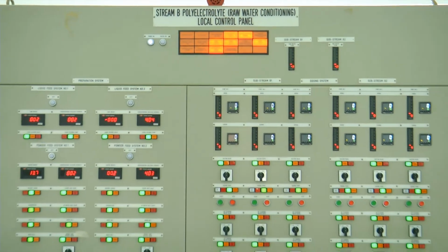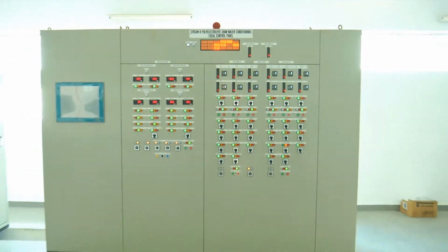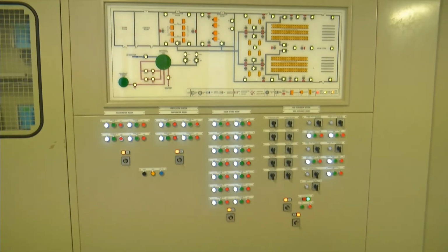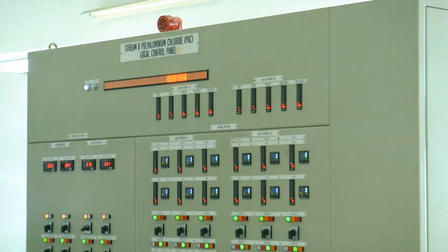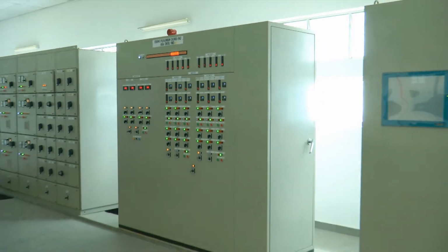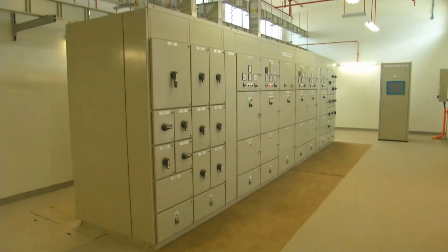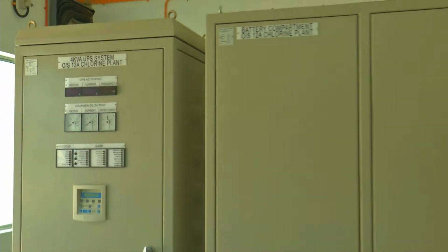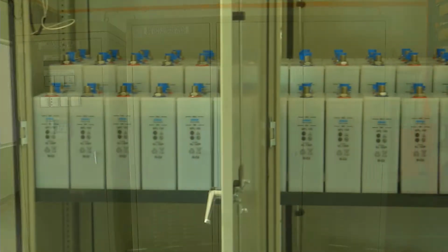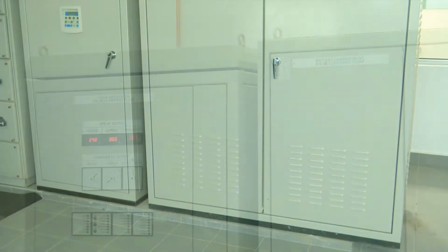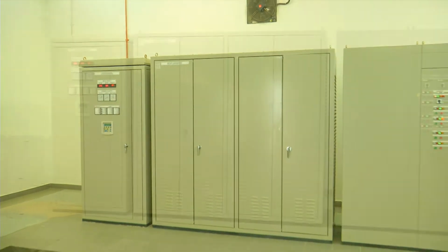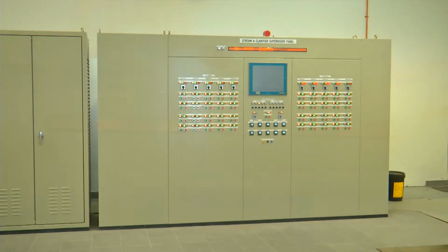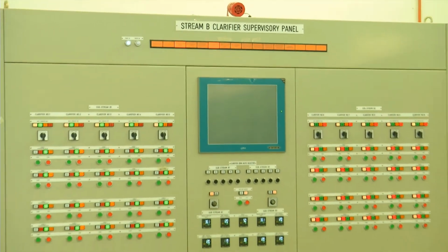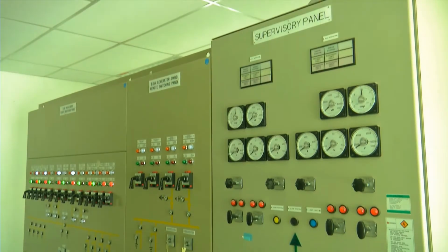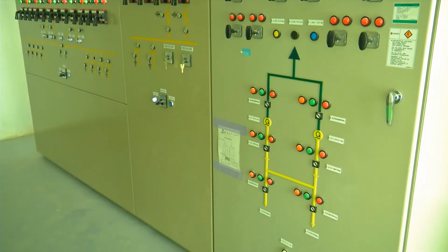Local plant control panels are used mainly as a local point to control motors and pumps in the plant. UPS system panel provides battery backup for the electrical control panels, when the electrical power fails or drops to an unacceptable voltage level. Supervisory panel is an overall monitoring of individual process controllers, which gives the operator an overall plant process view, and allows integration of operation between controllers.